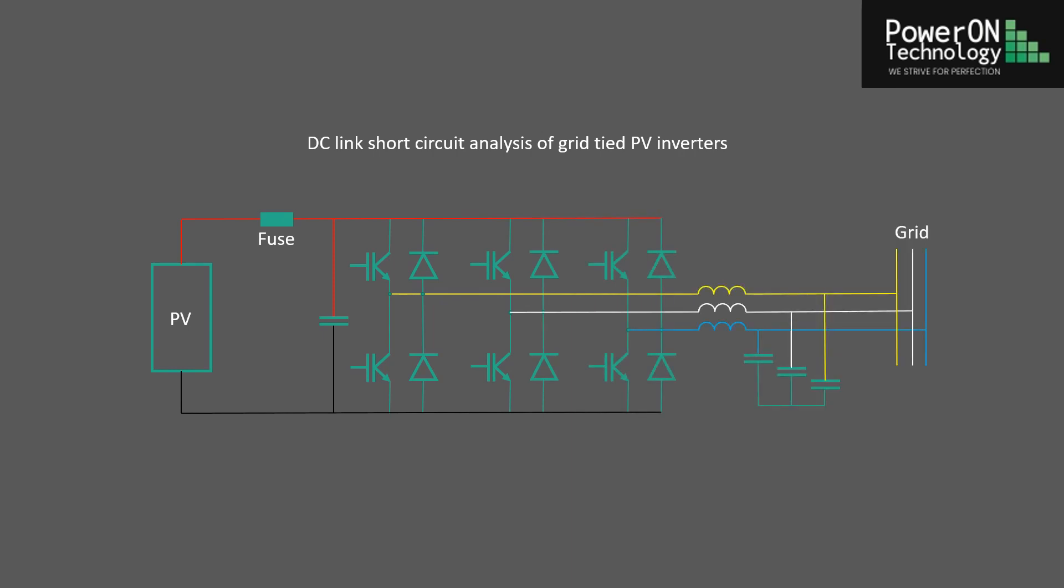This is what a typical grid-tied inverter installation looks like. The PV panel array feeds into a three-phase inverter. At the input to the inverter is a capacitor bank to filter out the three-phase current ripple. This is followed by the six IGBTs with their freewheel diodes and the output filter with inductors and capacitors. The output is connected to the three-phase grid.